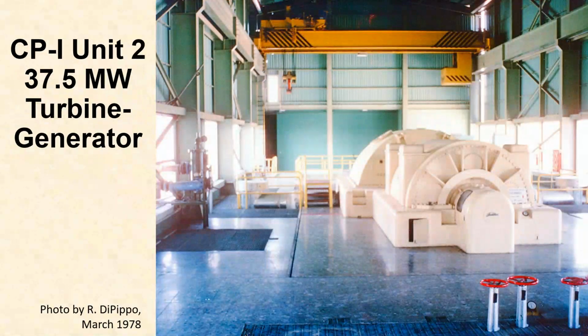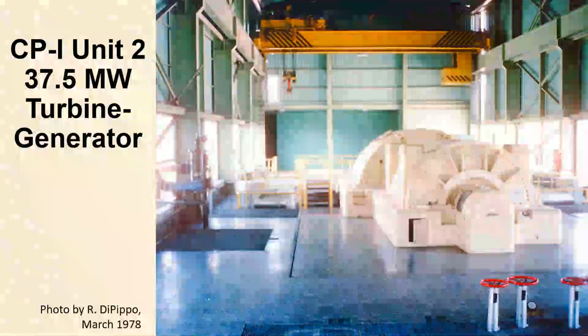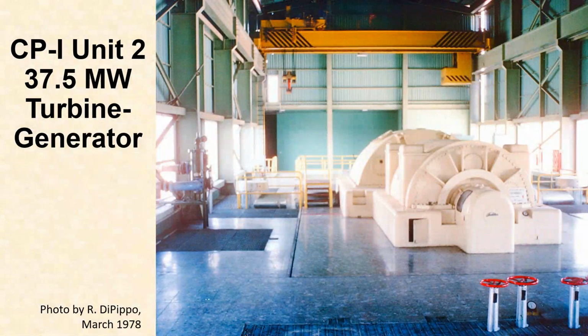The next slide shows the inside of the powerhouse with the generator and the turbine. The unit in front here is the generator, the turbine is behind it. The reason they used that barometric condenser was because at the time, that was the simplest way to condense. No moving parts inside. And it had been used at the Geysers, for example, in the early units, and they adopted it here. Once those units were removed, no further barometric condensers are used anywhere in the field, and all the units that we talk about are then using low-level direct contact condensers. Next picture, please.